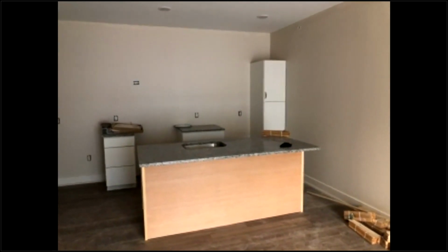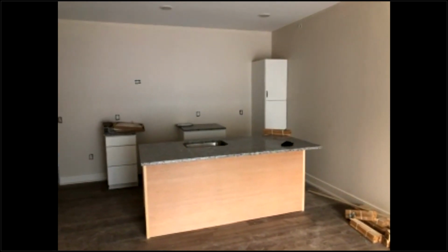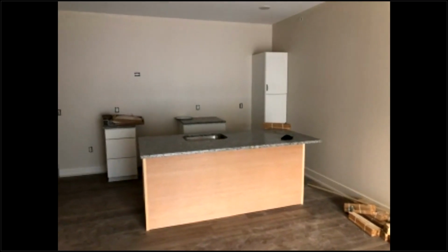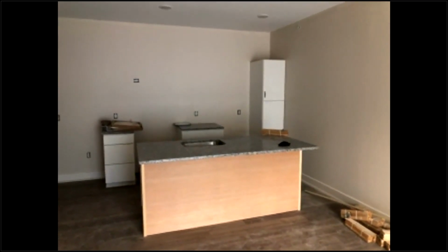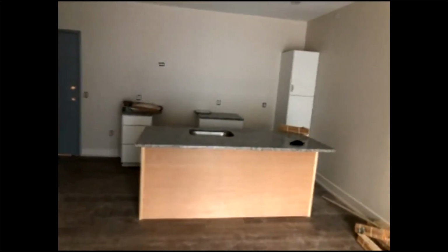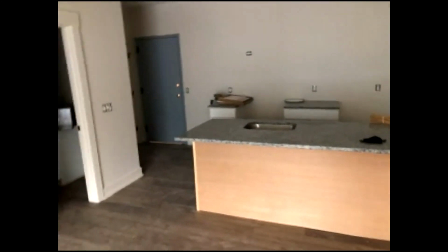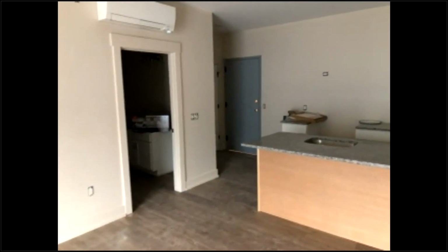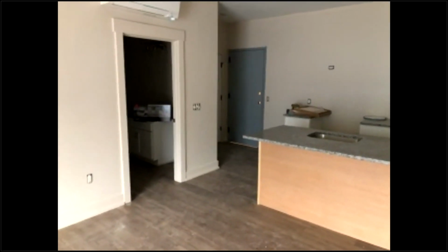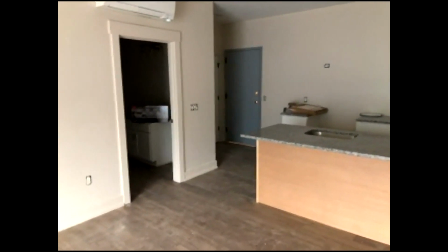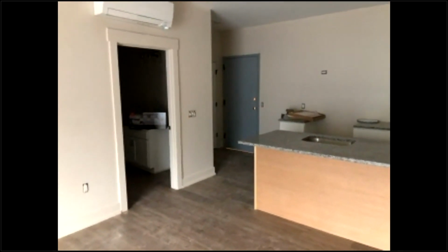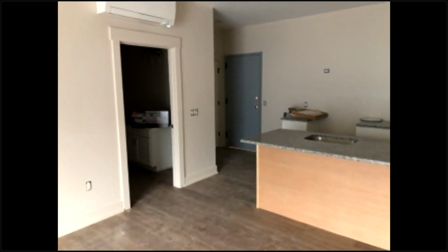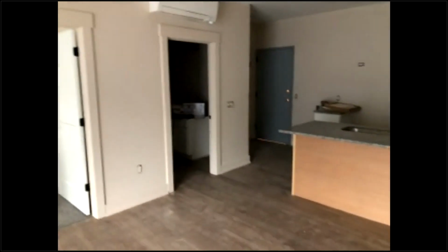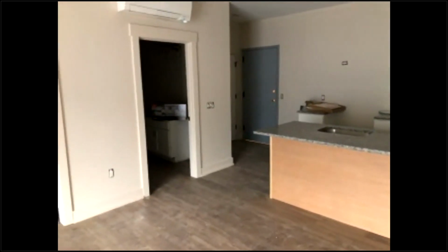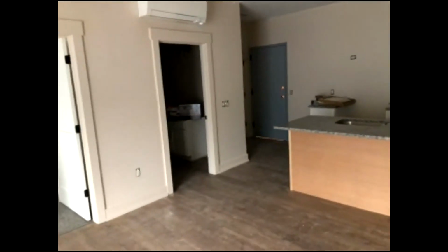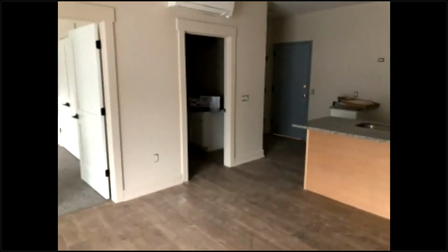What made you choose a ductless versus ducted system? Was there any concern about having two heads, one for each room? We did look at that and found the balance of overall efficiency and cost made more sense to have just one unit. We figured the space was small enough that to get true zone control like you'd have with multiple units, you weren't really going to get that anyway. It didn't make sense for a roughly 750 square foot unit to have one zone kept at 68 degrees and another zone allowed to get up to 73 or 74 in summer, or vice versa in winter. We figured that wasn't going to happen with the size of the unit.